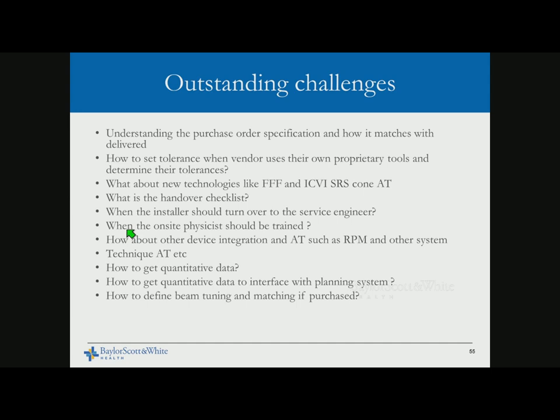There are also challenges around the handover checklist — when the installer finishes and hands over to the service team, and how this handshake should happen. As the clinical customer in the middle, when the handshake doesn't happen properly and things go wrong during commissioning, it's unclear who to call. Third-party device integration when you have devices sponsored through vendors also needs clarification. Most importantly is quantitative data — we need it for future reference and for transferring into planning systems.